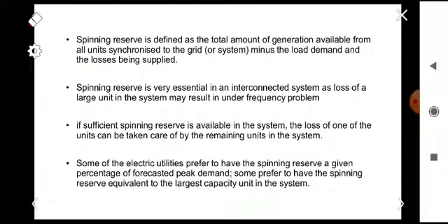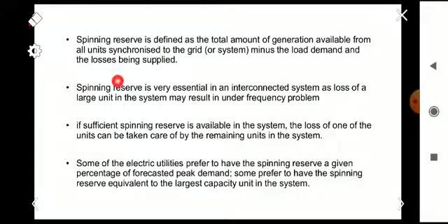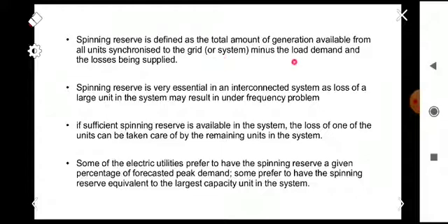The first constraint is the spinning reserve constraint. The spinning reserve is defined as the total amount of generation available from all units synchronized to the grid, minus the load demand and the losses being supplied. Spinning reserve is essentially additional generation that may be used in contingencies, equal to generation available from all units minus load demand minus losses.